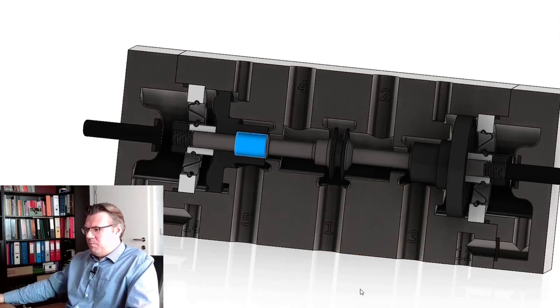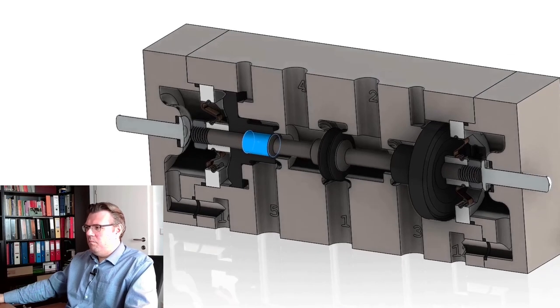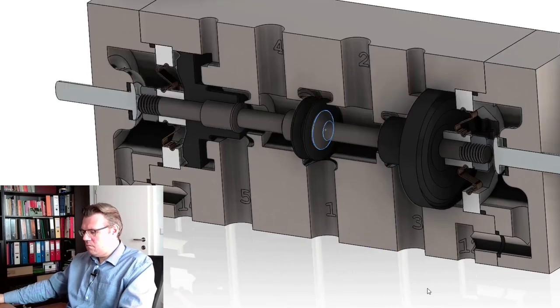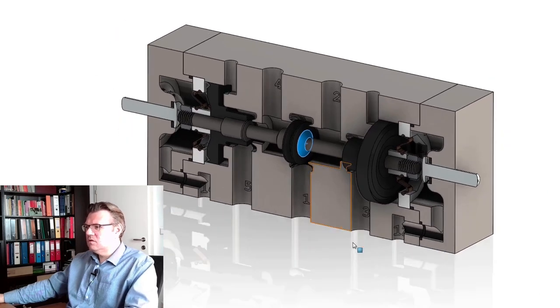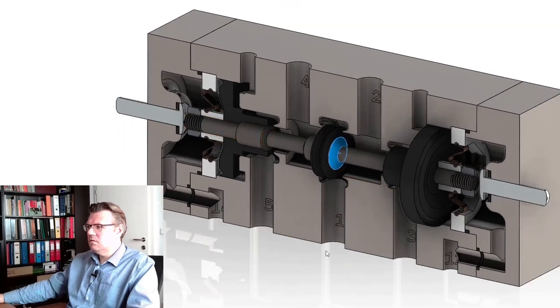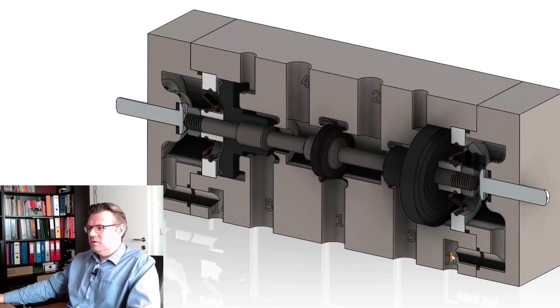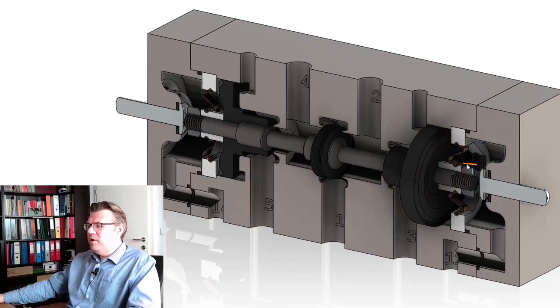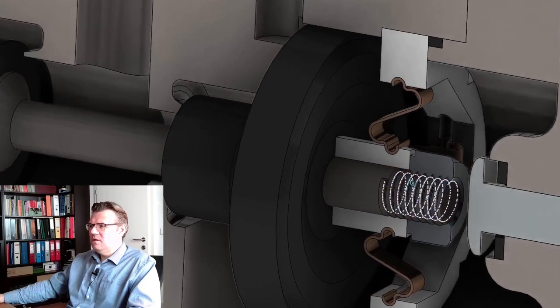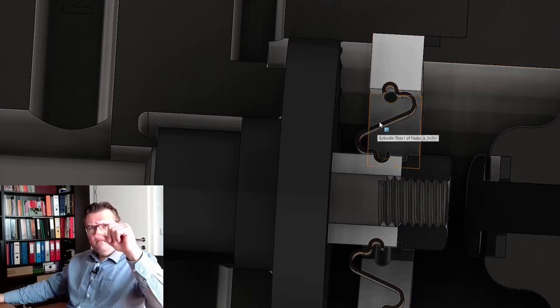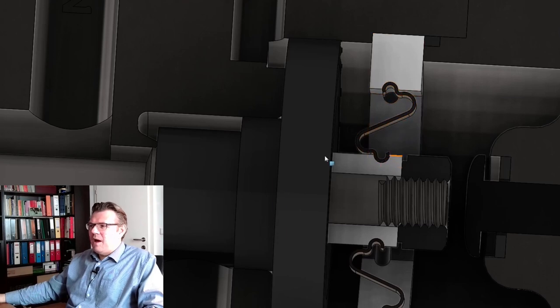So to summarize, let's apply pressure here, 1, 2, we'll move to the left. 1 and 2 are connected because it's the 1-2 line. 3 is sealed here. 4 and 5 are also connected. These springs here, let's have a look at these springs. They are helping. You see, this is a spring which will try to push apart, and since this is now a little bit left than this, if the spring tries to expand, it will also move to the left, so it will keep the piston in place.